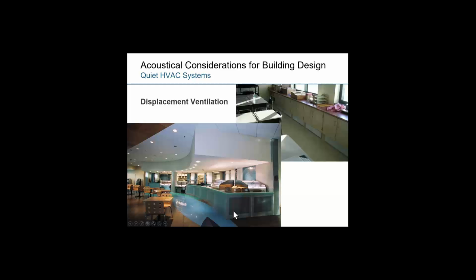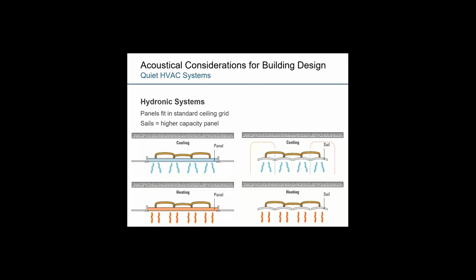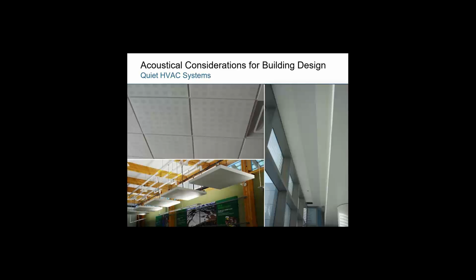And you can see on the image here, comparing a mixing ventilation system with an overhead supply and return system to that of a displacement diffuser, lower, closer to the occupants within the space. A couple actual examples of displacement ventilation are shown here, where there are typically displacement ventilation diffusers installed closer to the occupants, and air is introduced at very low velocities at a comfortable rate into that area, conditioning a space without maybe the noise that might be present in a traditional VAV system. You can see highlighted there. Another system that can often have low sound criteria is hydronic systems. Chilled beams or radiant panels that have the power of water being used in conjunction with lower velocities and volumes of air can help create a quiet space as well.